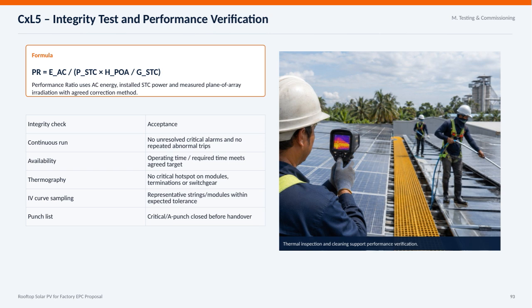This ratio helps us measure how efficiently the system converts sunlight into usable electricity. Now, the integrity check covers several critical points. The system must run continuously without unresolved alarms or abnormal trips, and the availability, meaning the actual operating time, must meet our agreed targets. Thermal imaging is used to ensure there are no critical hotspots on modules, terminations, or switchgear, which could indicate potential failures. We also sample IV curves from representative strings and modules to confirm they're within expected tolerances.